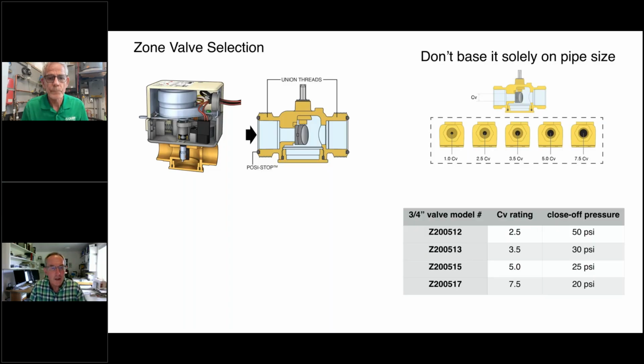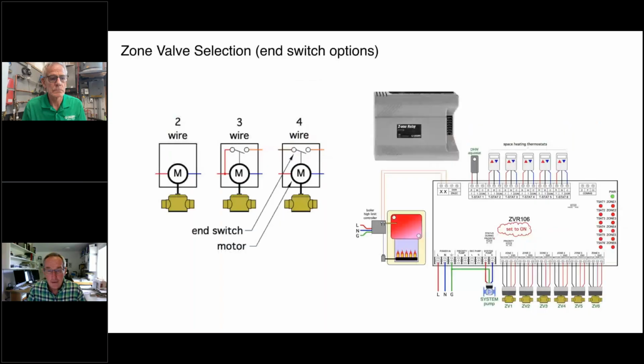Okay, real quick, electrically, there are three types of zone valves on the market. Caleffi basically makes a 2-wire or 4-wire version. The 3-wire version was around. I think you can still buy these probably as replacements. In the 3-wire valve, one side of the end switch is wired to the wire that also operates the motor in the valve. So that can be used in some circumstances.